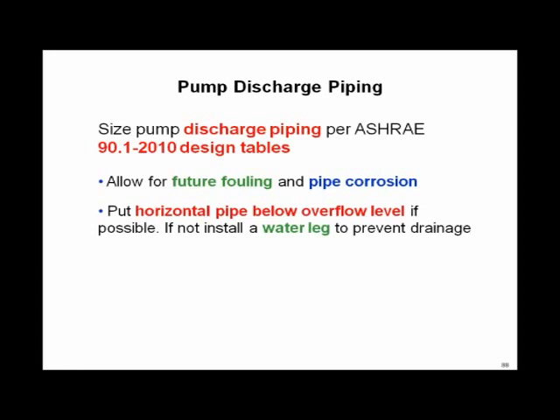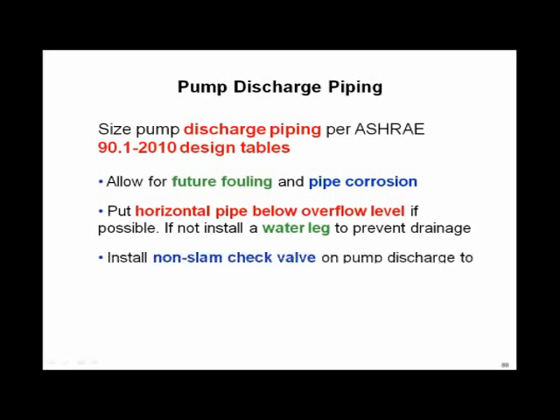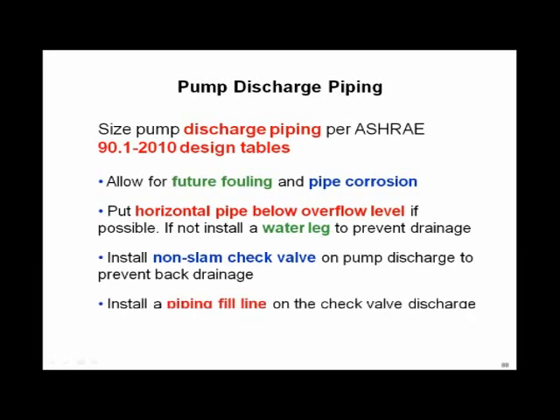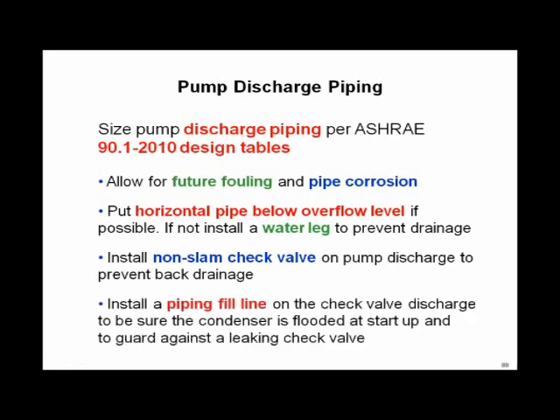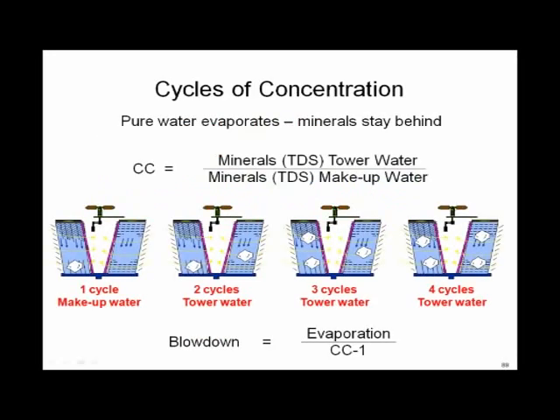If you've got horizontal piping, as we showed you in that drain down example, make sure there's a water trap or it's below the tower. And we'll look at that picture again in just a minute. Make sure you've got non-slam center guided check valves on the discharge of your pump. You want to make sure they don't leak back. You've got to make sure you've got good quality check valves. Triple Duty valves work right here. Install a pipe filling line above the check valve if you're worried about trash, so you can keep everything primed.